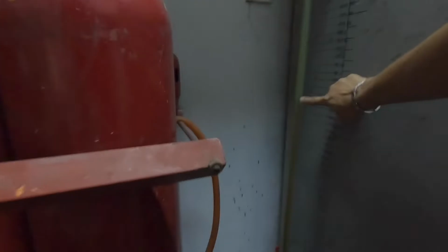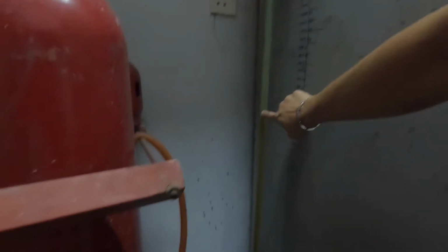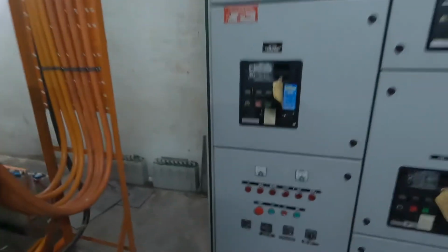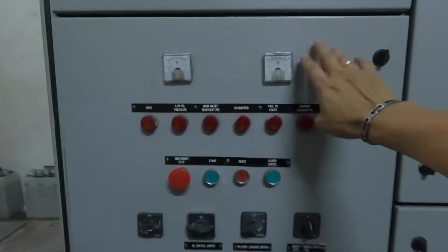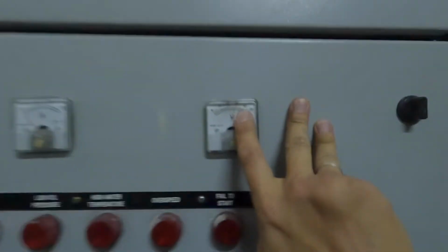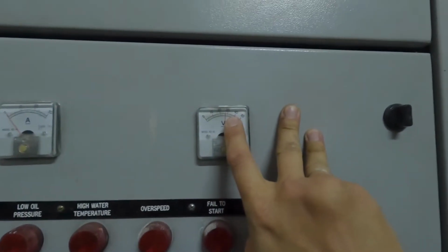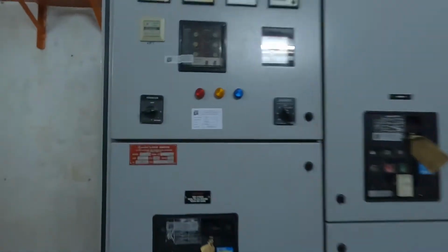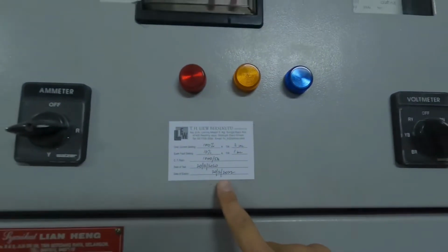The current fuel is almost about 50%. Okay, advisable to top up back above 50% if possible, but 50% is still okay. Okay, here we have the genset AMF panel, and here is the battery voltage. Currently is about 28 volt. We will have a fine measurement using the voltmeter. Calibration, okay, up to date.